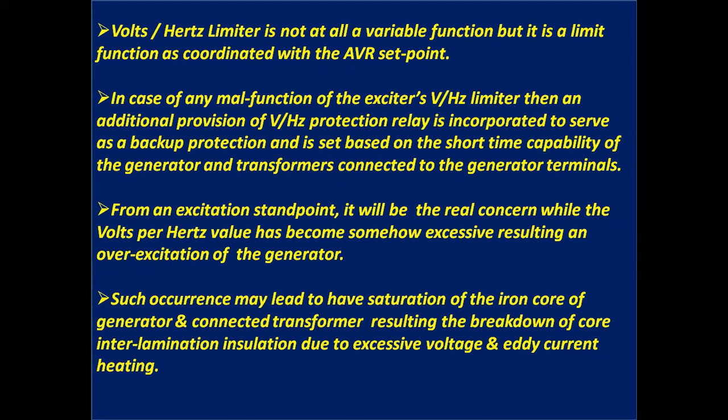In case of any malfunction of the exciter's volts Hertz ratio limiter, then an additional provision of volts per Hertz protection relay is incorporated to serve as a backup protection and is set based on the short time capability of the generator and transformers connected to the generator terminals.